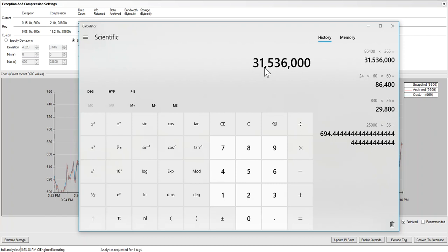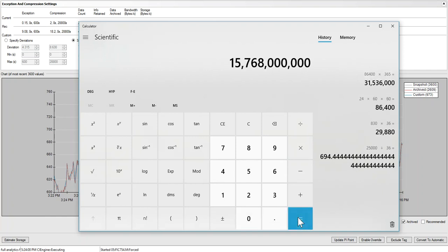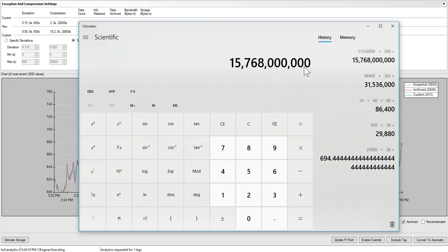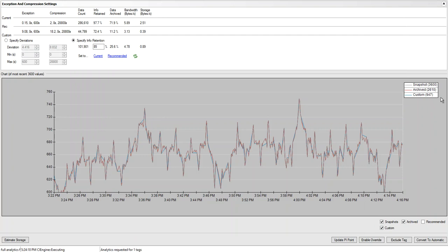I just recently did a data pull out of a PI system and grabbed over 500 tags for, actually, no, I'm sorry, I did it only for like 3 months, and I did it at 5-minute intervals. Imagine doing 500 tags for a year at 1 second fidelity and not doing any kind of compression. So I multiply that times 500. Okay, you're going to collect 15 billion data points, and I just showed you you don't need all of them to replicate what's going on in the process.